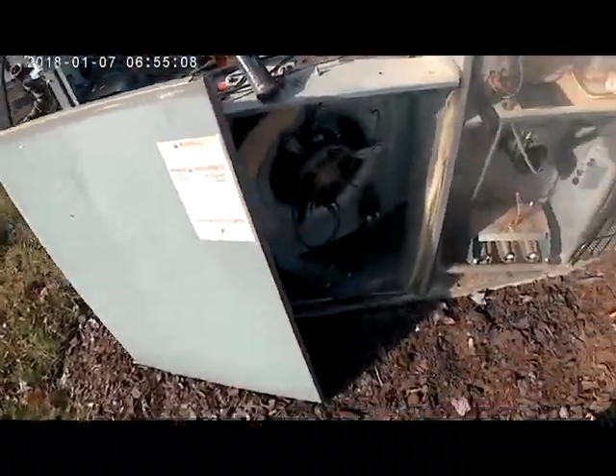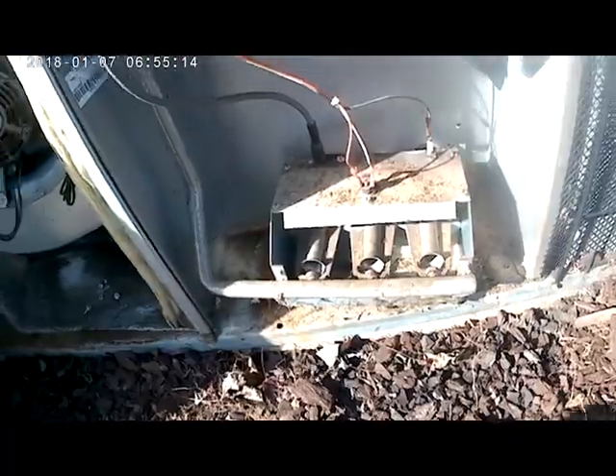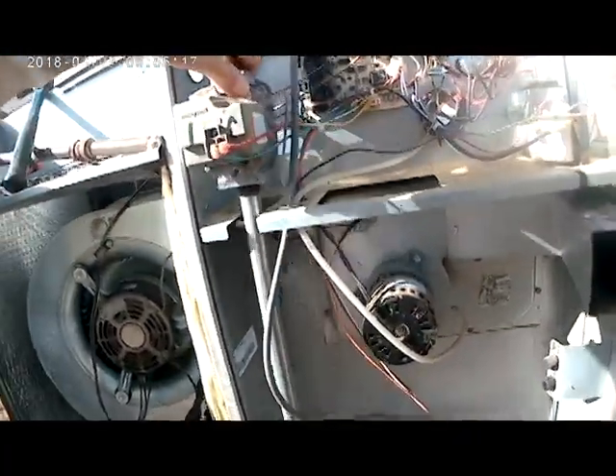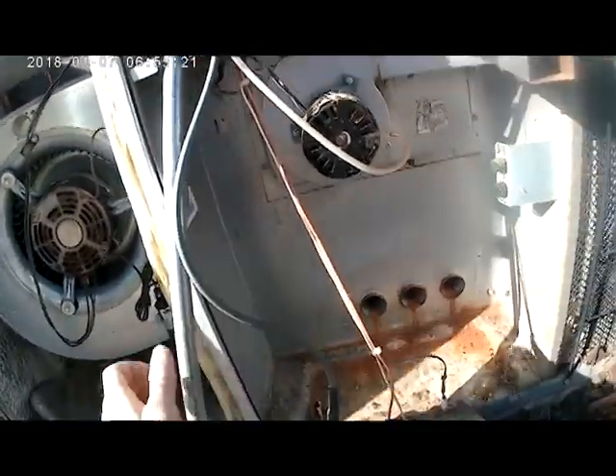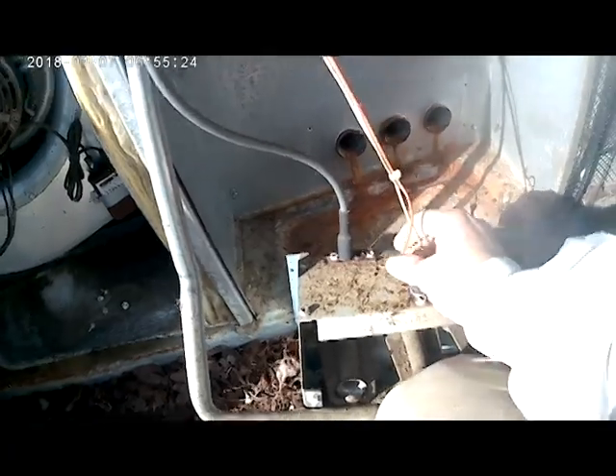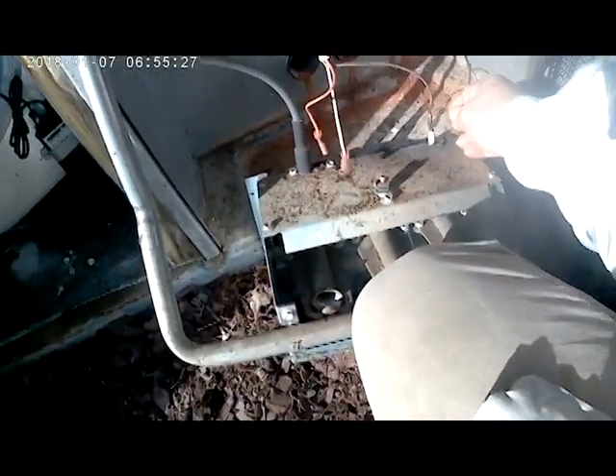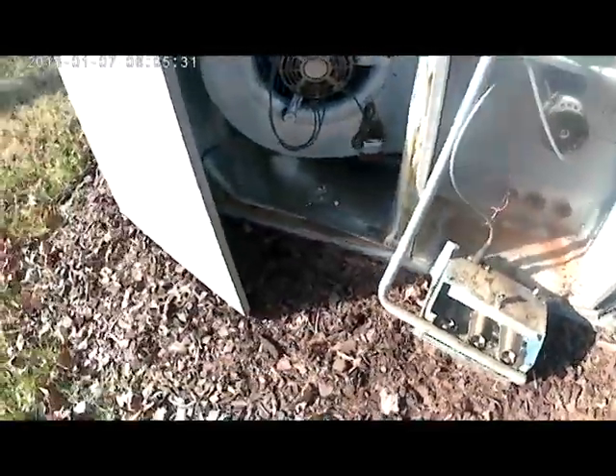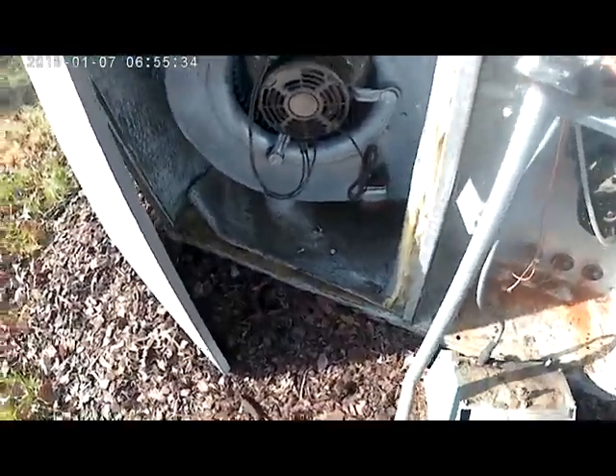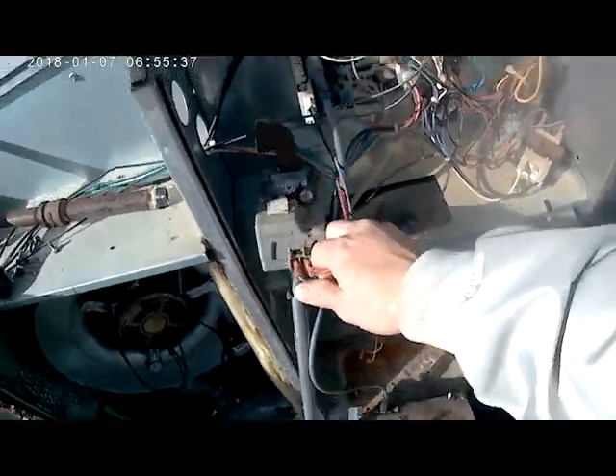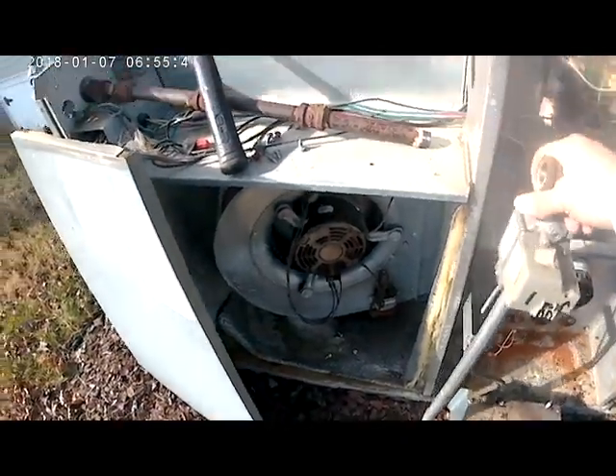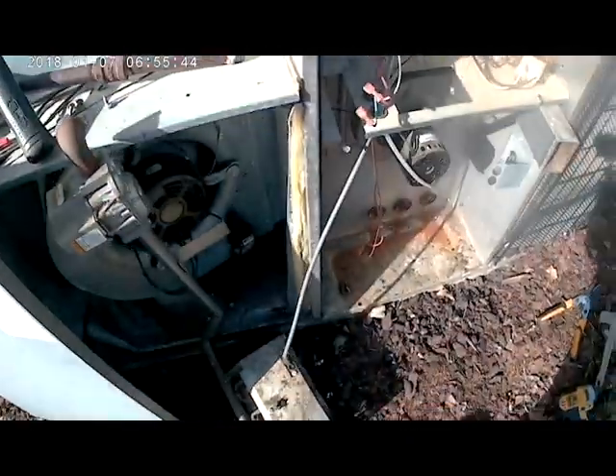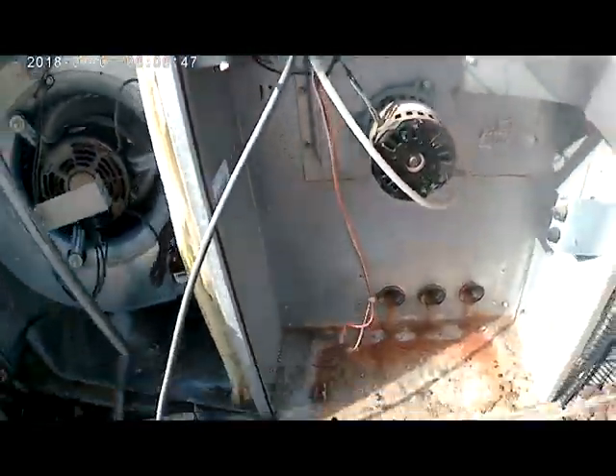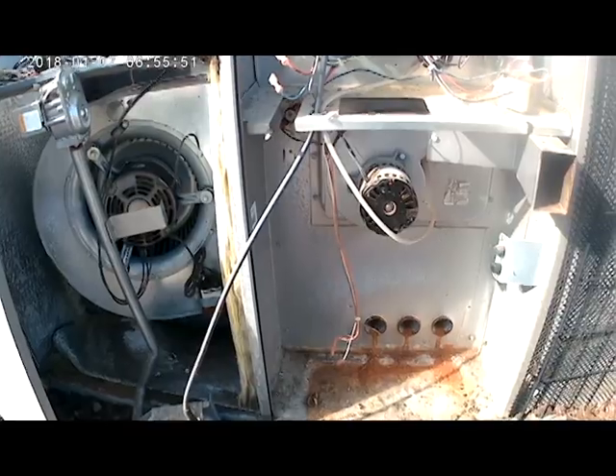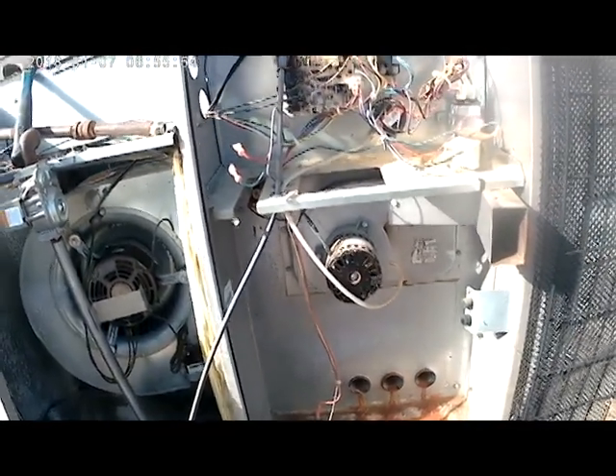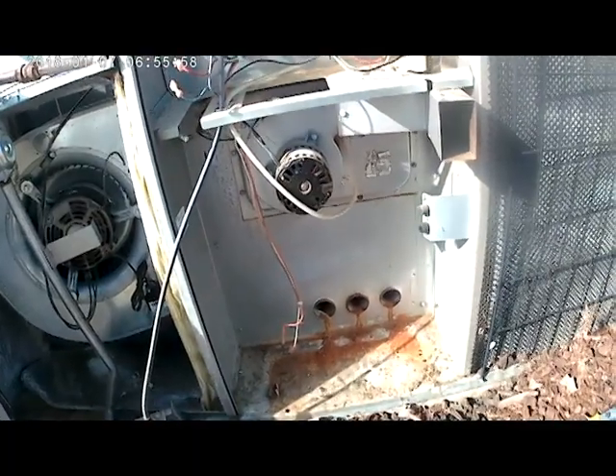Okay, I ended up having to pull this door off. We had to unloosen the burners and took the gas line off, so we move that out of the way. We've got our wires here - we want to take the wires off our float switch, off our flame sensor, and off our gas valve as well, so we can just set this over to the side. We're going to leave our line for the spark igniter up right now, just until we can figure out what else needs to be taken loose.